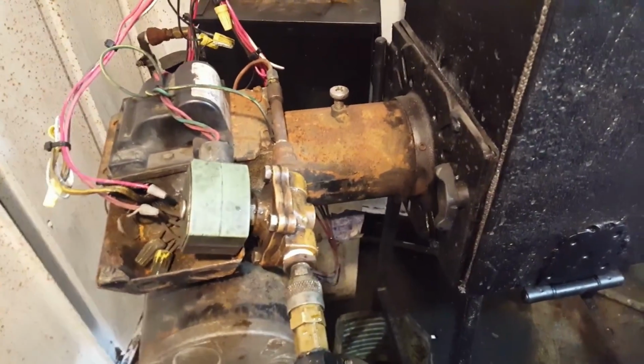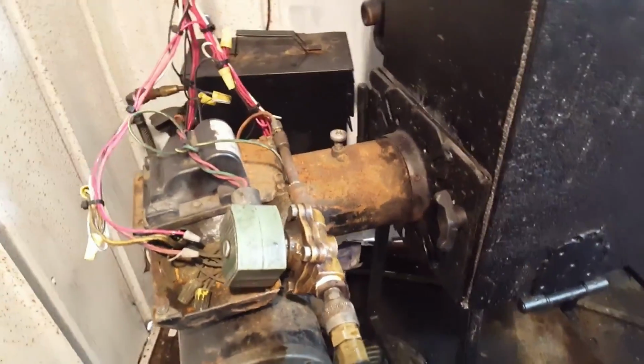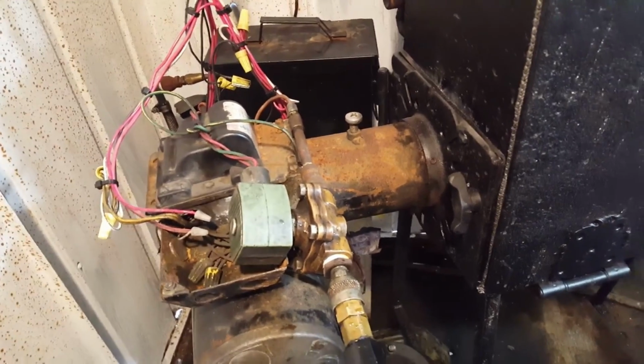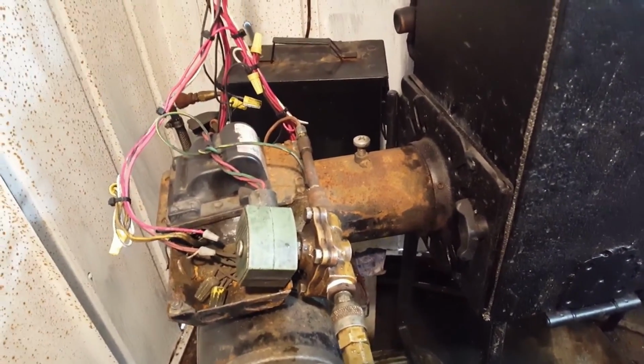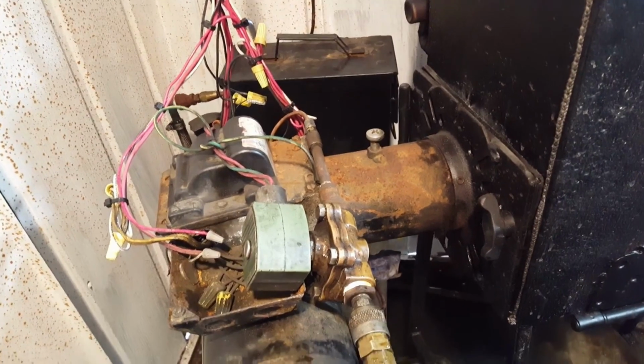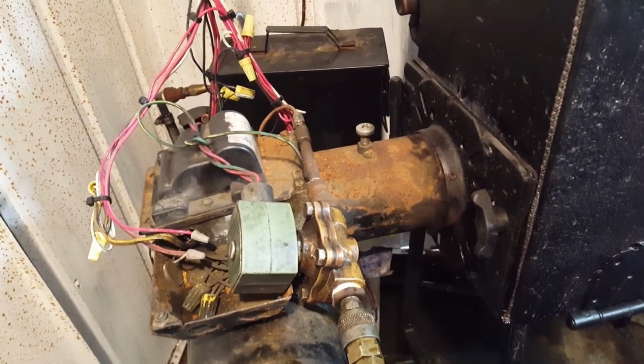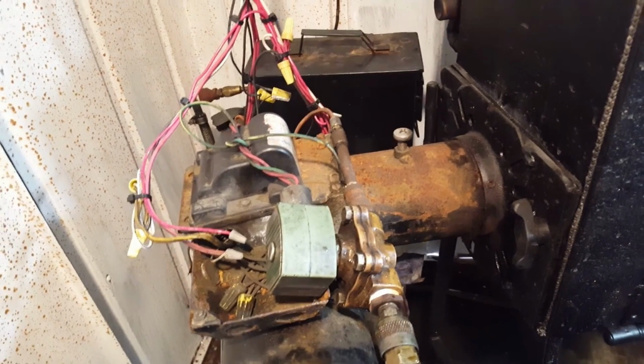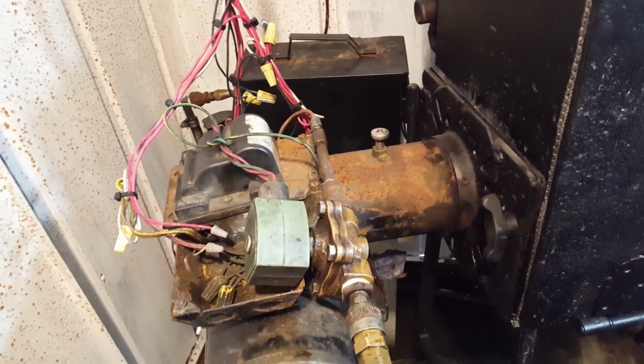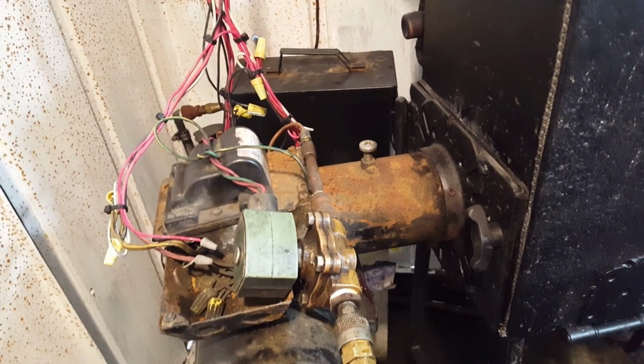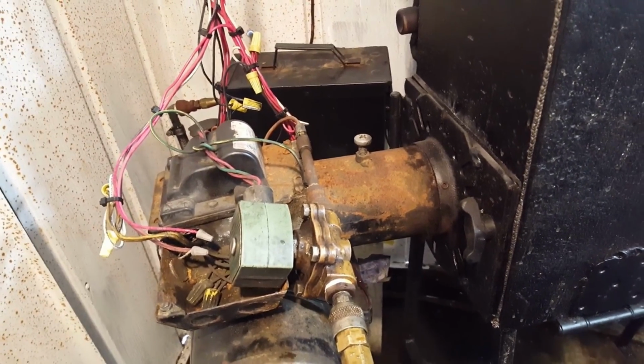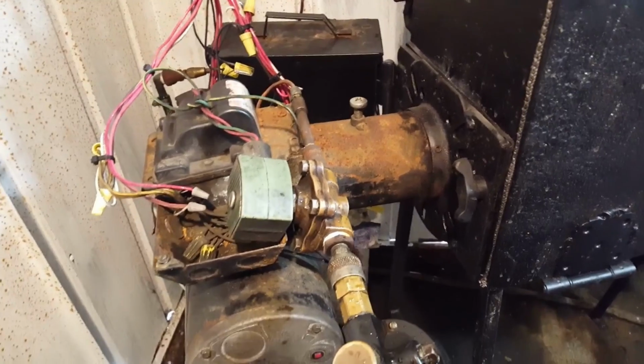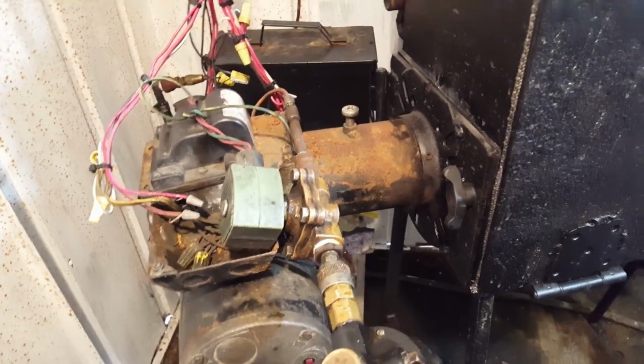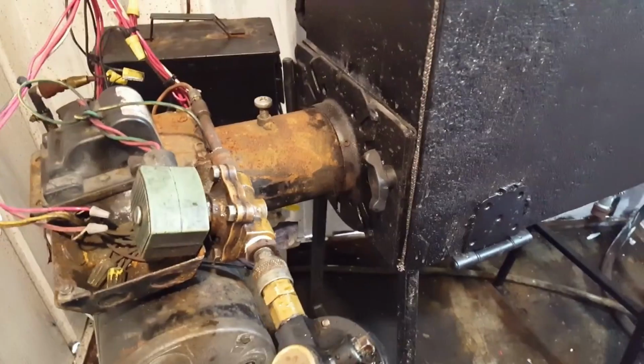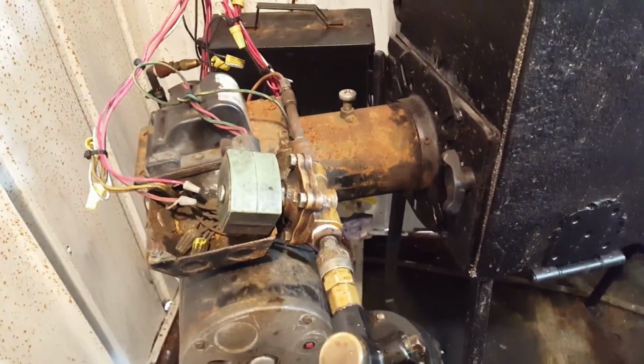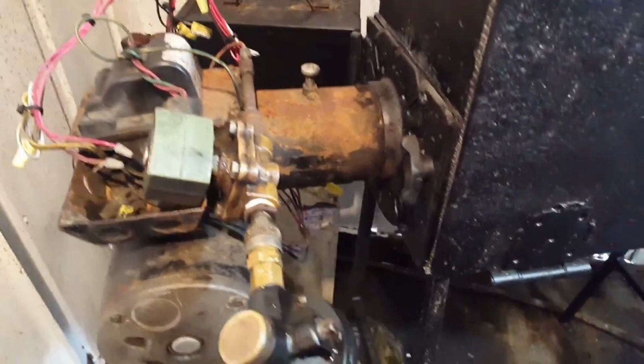Also, on that flame sensor, I've got the PLC basically running a check on it to make sure that it ain't shorted out when the burner ain't running. And here's why. Because if that flame sensor gets shorted out and then the burner gets a call for heat, everything starts up but it doesn't light, but it thinks it's lit because that flame sensor is shorted out, well, this sucker will sit here and spray oil in this heater all day long. And I got 25 gallons of oil over here, and that's a lot of oil. But here's another problem with that.